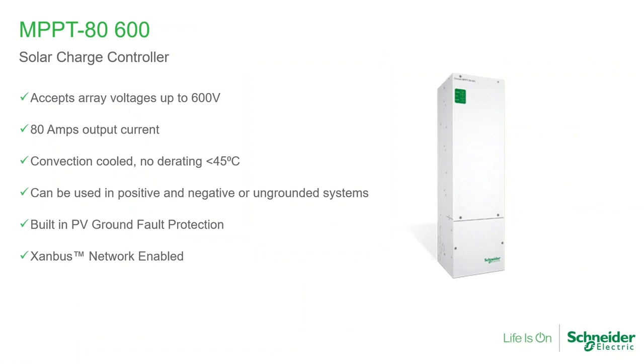The uniqueness about the MPPT-80 600 is that it can accept up to 600 volts, which makes it more similar to what a residential grid-tie inverter is. Typically with the MPPT-80, you would use strings of 10, maybe strings of 12, depending on the module. Today modules are getting bigger and bigger, and usually the typical installation has one or two strings.